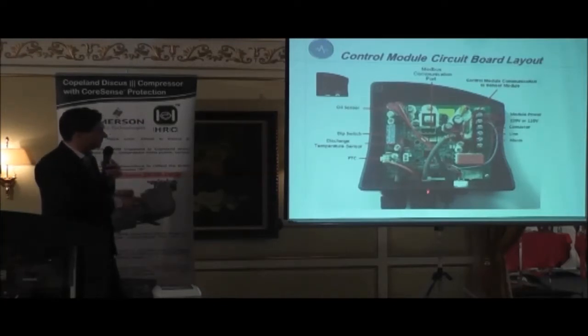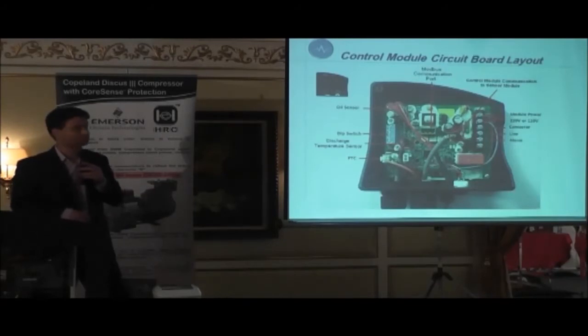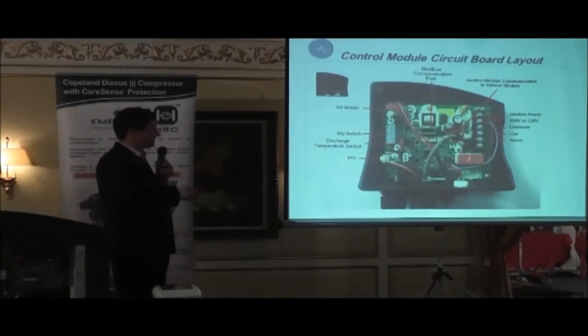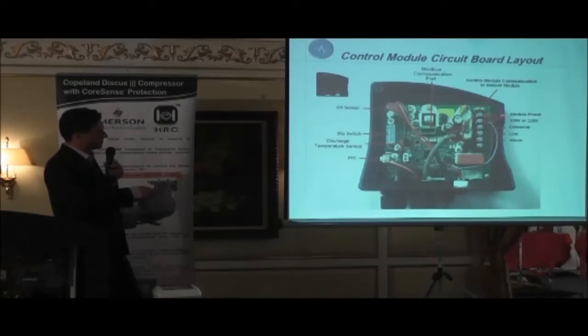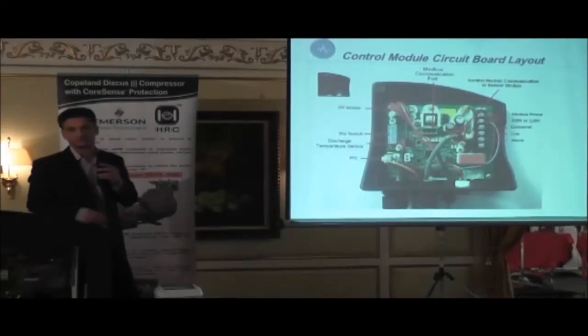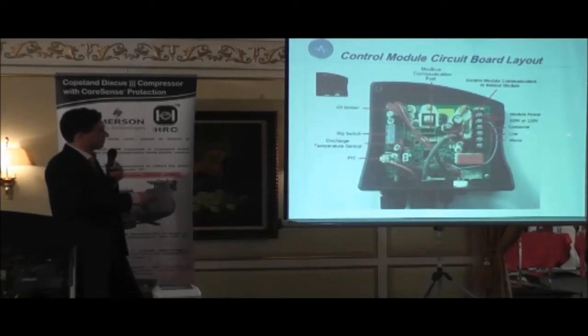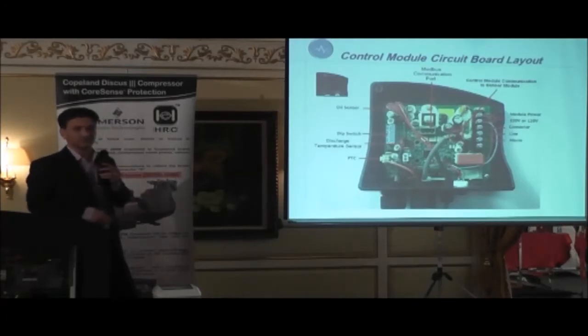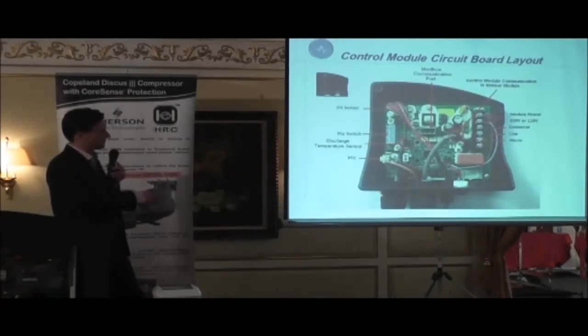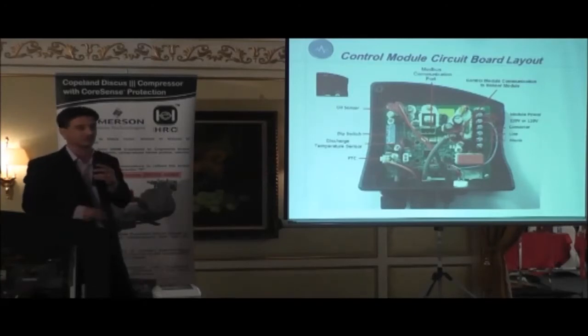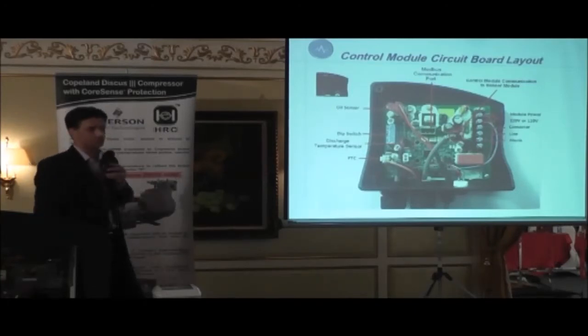Here we have the connection cable from the sensor module to the control module. And here we have our high voltage supply. Okay? There's 6 terminals on here. So you would bring in your 220 volt supply, live and neutral if you have a neutral, or just L1 to L2. Your line is your control. So you would wire in your control through the line. If everything is okay, you energize your contactor. If the compressor trips, it energizes the alarm output. You can wire that if it's required. The last terminal is your ground connection.